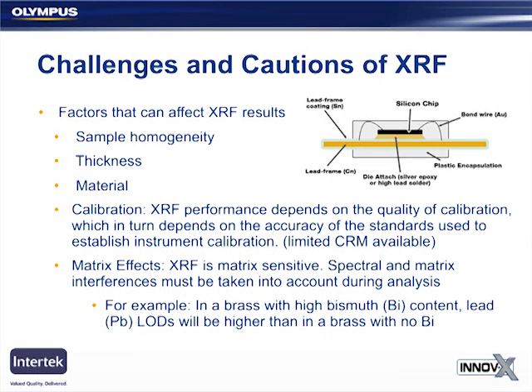In XRF, we're usually looking out for what are called matrix effects. These are the effects that most of the elements that are in your sample are having on the few elements that you're actually looking for. Sometimes elements can interfere with each other, can raise detection limits, or cause deviation of results. The calculation software that comes with the analyzer normally takes care of all of these, but there are some cases where you may want to be aware of what's going on.